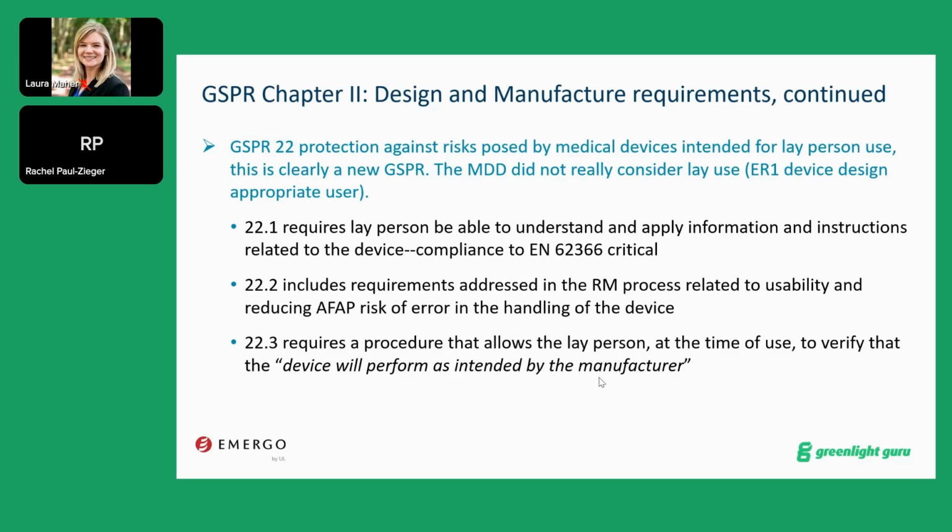Previously, the MDD did not really consider lay use. So there might be instruction that can be understood by a layperson. There are requirements to have this in the risk management process related to usability, and that the user can properly use the device. So there are more extended requirements here.